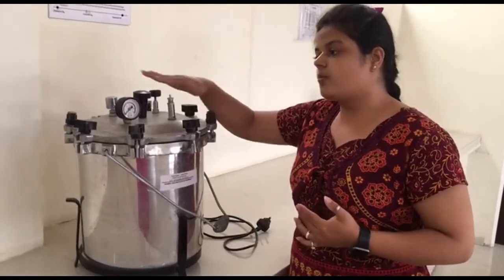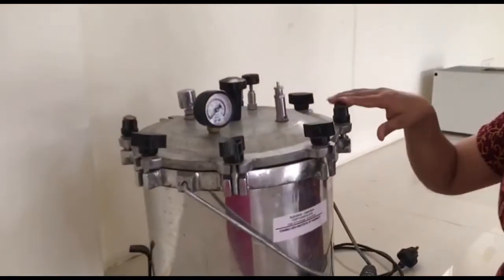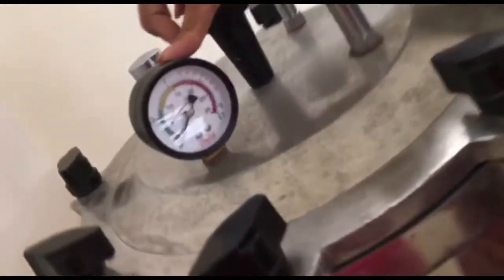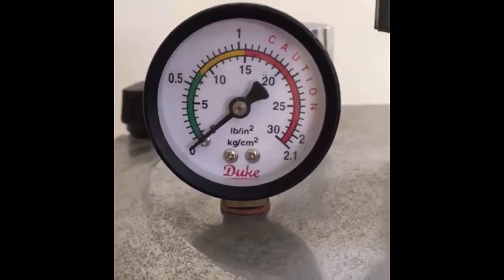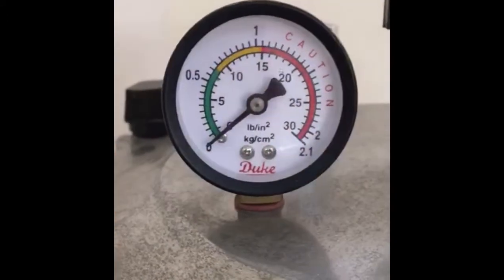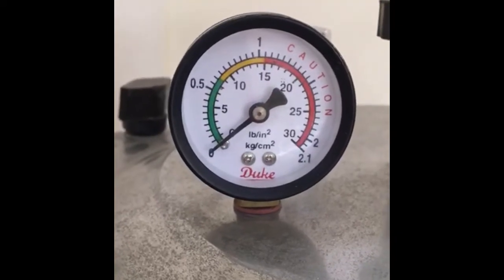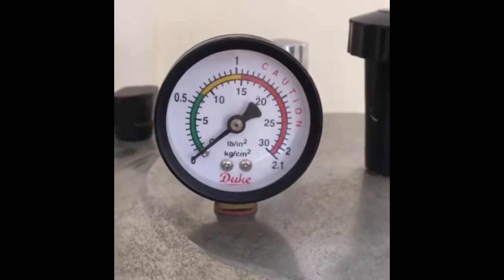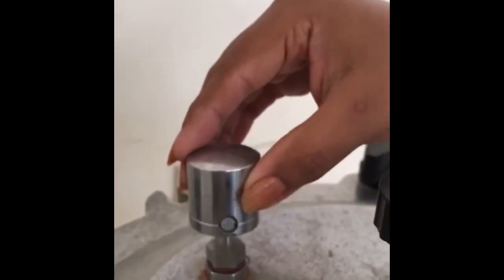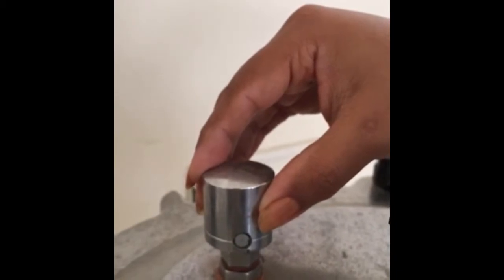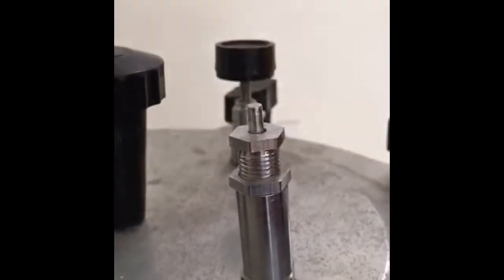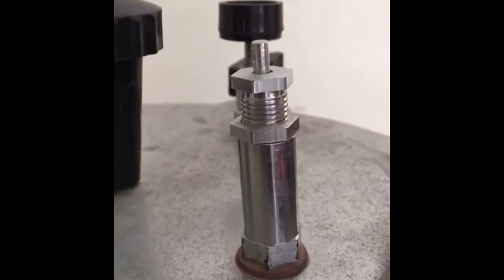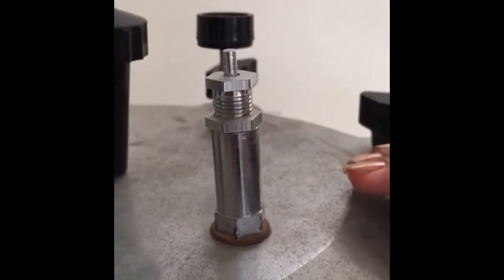Now on the top of the autoclave you can see various units. This is the pressure valve. This pressure valve indicates the pressure inside of an autoclave. As we know, the basic principle or efficacy of an autoclave depends on the pressure only for sterilization purpose. This is the vent or the pressure whistle, same as the home cooker. Now this is the safety valve.